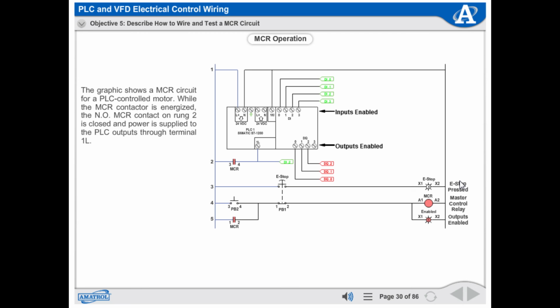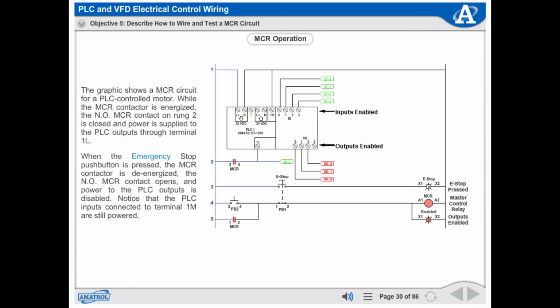The graphic shows a master control relay circuit for a PLC-controlled motor. While the master control relay contactor is energized, the normally open master control relay contact on rung 2 is closed, and power is supplied to the PLC outputs through terminal 1L. When the emergency stop push button is pressed, the master control relay contactor is de-energized. The normally open master control relay contact opens, and power to the PLC outputs is disabled. Notice that the PLC inputs connected to terminal 1M are still powered.